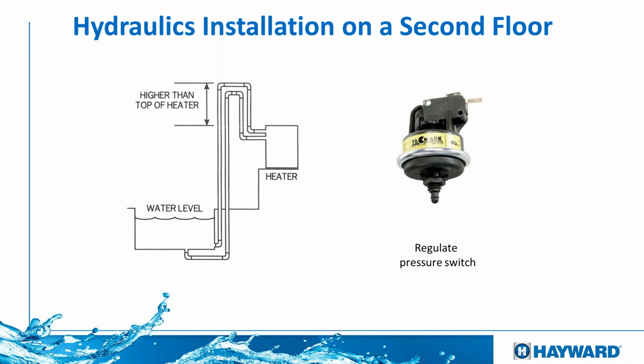So if we have a heater below a pool, let's imagine we have a pool on the second floor, and it's a pretty good sized pool. Let's talk about, I don't know, 30,000 gallons, for example. Well, if we have that, maybe the weight of that body of water is going to make this switch close without having any flow. So we need to adjust this water pressure switch. It's got a little wheel on it.